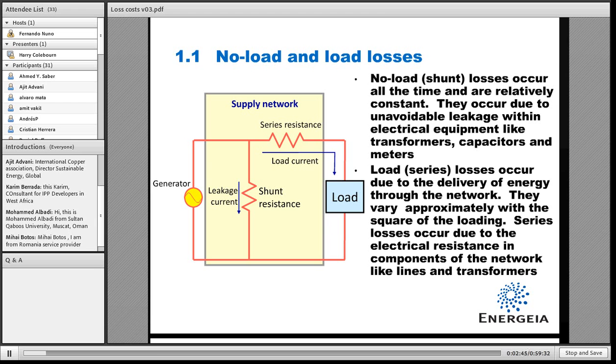The shunt losses or no-load losses remain constant, and load losses vary approximately with the square of the electrical flow or with the square of the load.